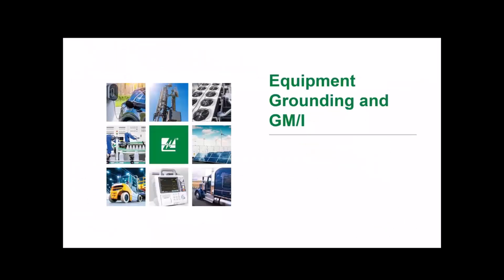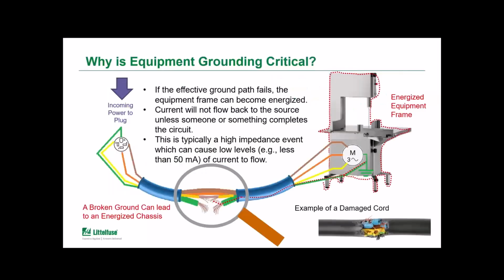So I want to focus a little more on the equipment ground conductor. Specifically, we can go through a few cases here just to compare the operation of a Class A and a Class C special purpose GFCI side by side. Again, and I know I'm reiterating this point, I want to make sure it's clear that the purpose of that effective ground path is to provide a low impedance path for ground fault current to flow through. The low impedance allows more current to flow and hopefully trip or even blow the upstream overcurrent protection very quickly when there's a fault.